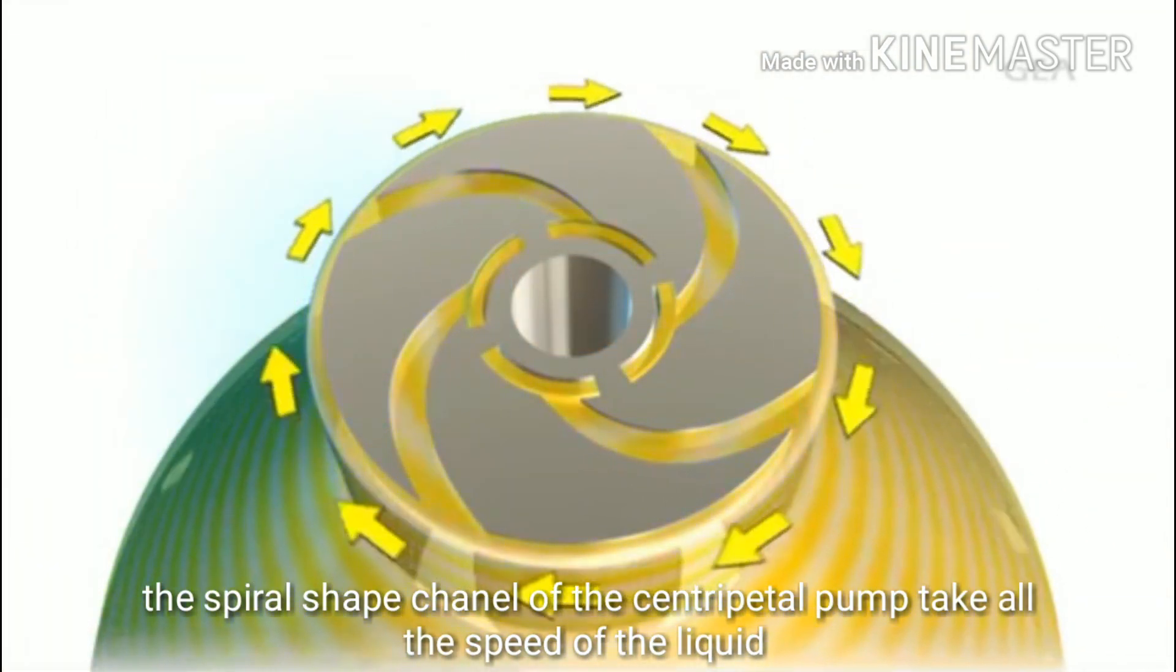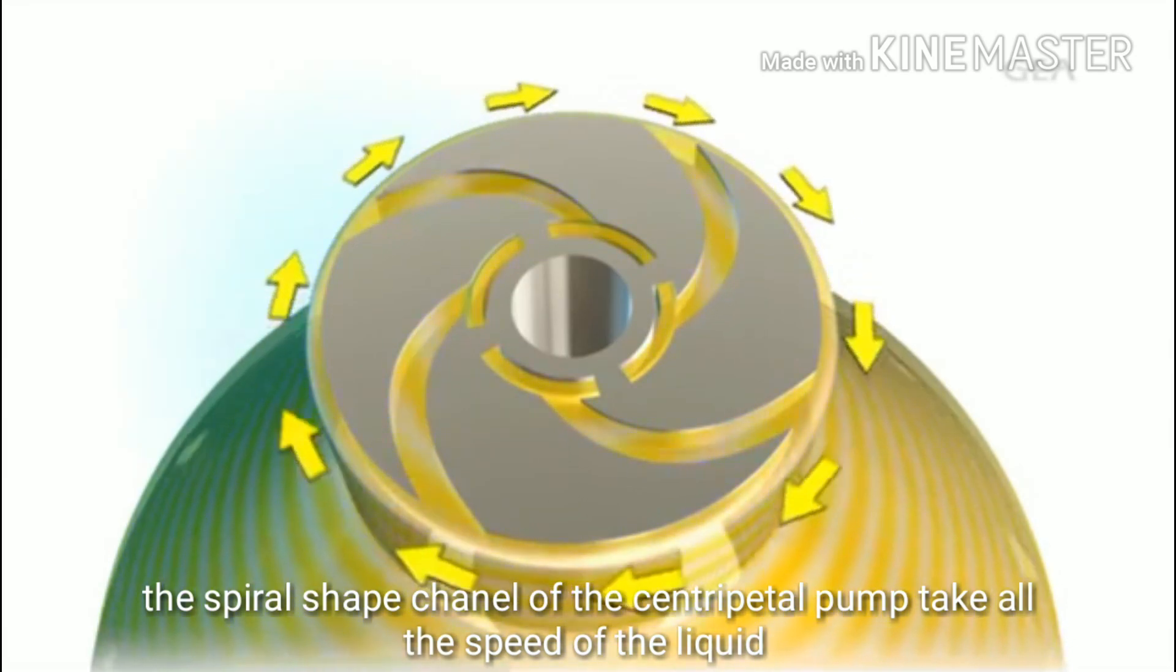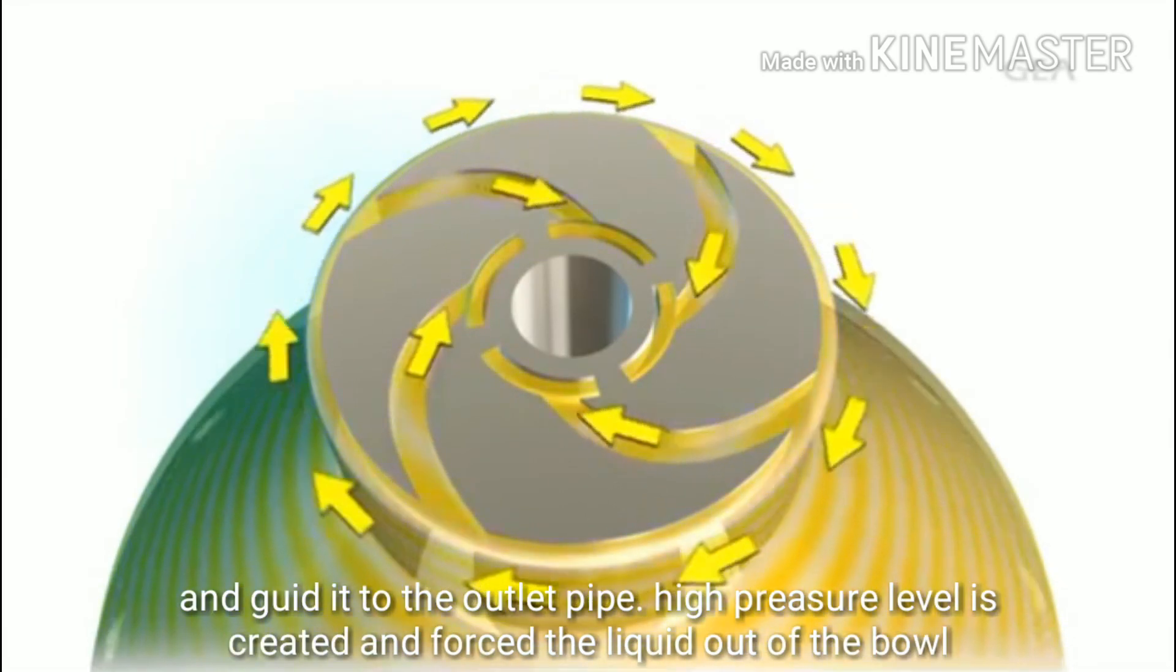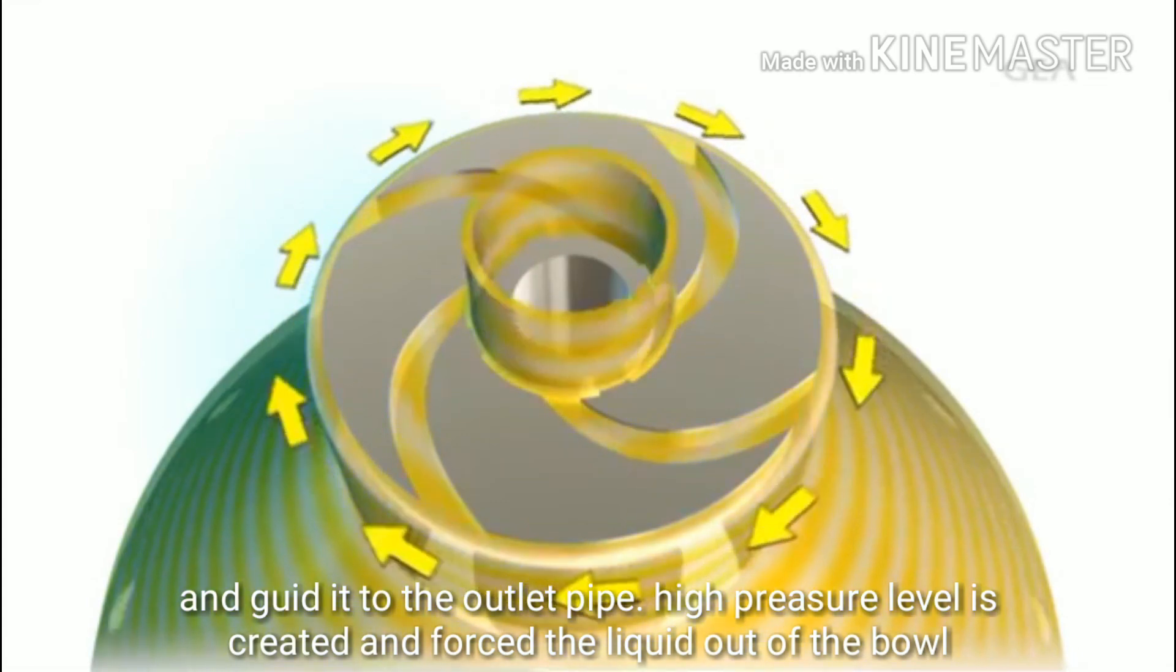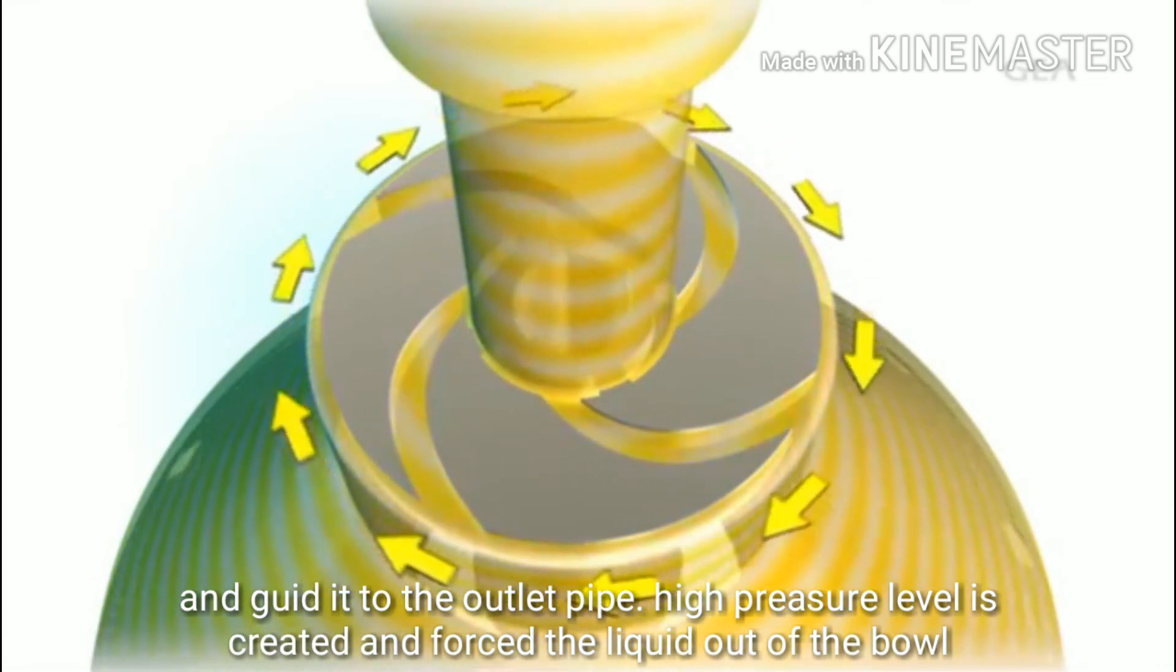The spiral shaped channels of this centripetal pump take up the speed of the liquid and guide it to the outlet pipe. A high pressure level is created there which forces the liquid out of the bowl.